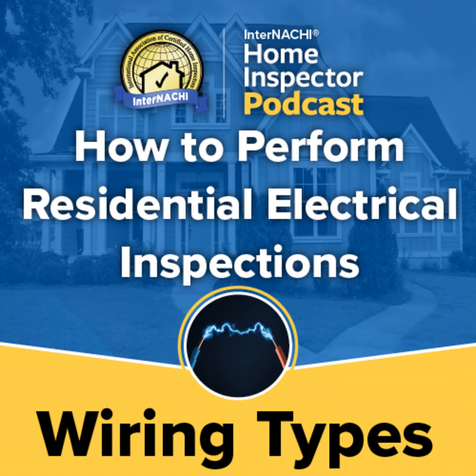UF, underground feeder cable. UF stands for underground feeder cable. UF is a type of electrical cable commonly used in outdoor and underground installations. What is UF cable? Construction. UF cable is designed with insulation that surrounds each wire individually and is encased in a tough, moisture-resistant outer jacket. Material. Often has conductors made of copper and can handle various amperage ratings depending on the gauge. Installation. Can be directly buried in the ground without needing additional conduit, making it ideal for underground or wet location installations.